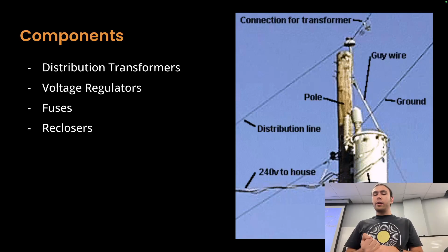You also have things called reclosers. These are essentially intelligent automatic circuit breakers. While they differ from some of the more advanced circuit breakers doing things automatically, essentially they just do automatic circuit breaking. Their main purpose in the distribution phase is that if a tree branch touches the wire without taking down the whole power pole, that causes a short. The reclosers are really quick at detecting this and turn off the power for a brief second the instant they detect the short, then reconnect once the branch comes off. That's also why they have to cut tree limbs back when they get close, because the reclosers will start going off constantly from the branch hitting the line.